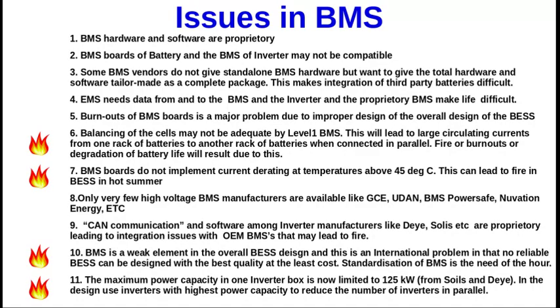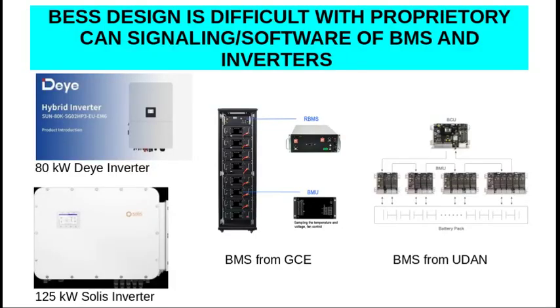Point number 10. BMS is a weak element in the overall BESS design, and this is an international problem in that no reliable BESS can be designed with the best quality at least cost. Standardization of the BMS and inverters is the need of the hour. Point number 11. The maximum power capacity of one inverter box is now limited to 125 kilowatt, both from Solis and from Deye. In the design, always use inverters with the highest power capacity to reduce the number of inverters in parallel. BESS design is difficult with the proprietary nature of the CAN signaling or software of the BMS manufacturers and the inverter manufacturers.